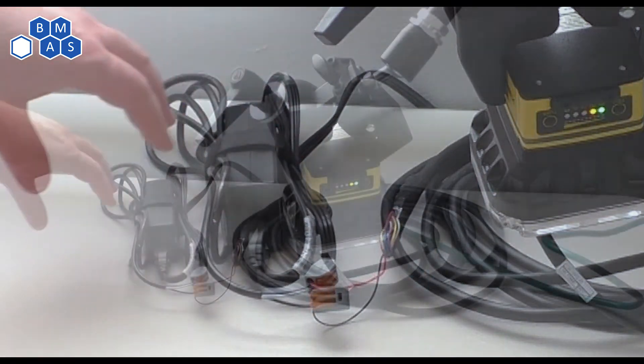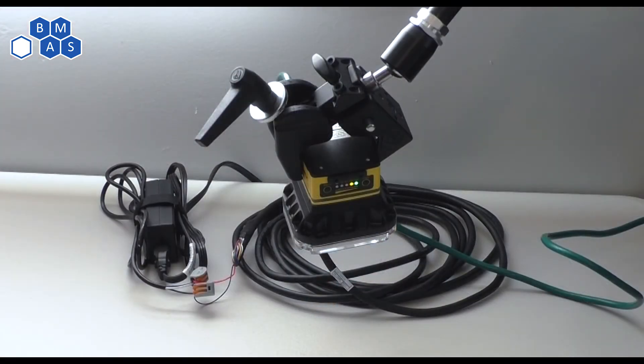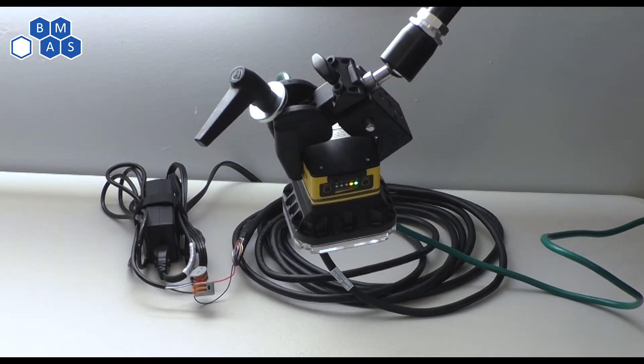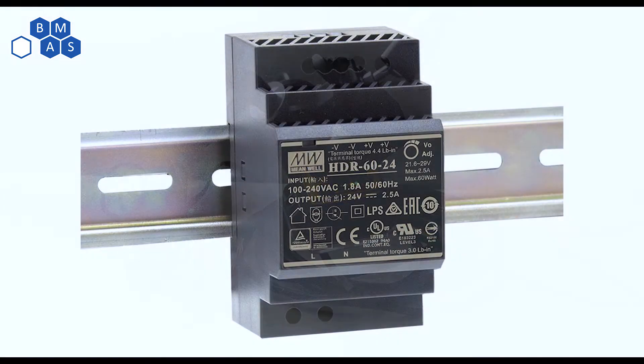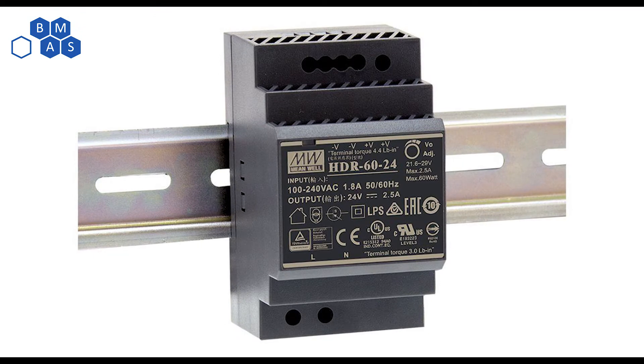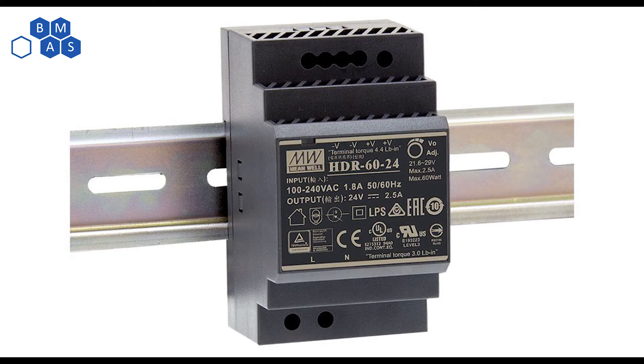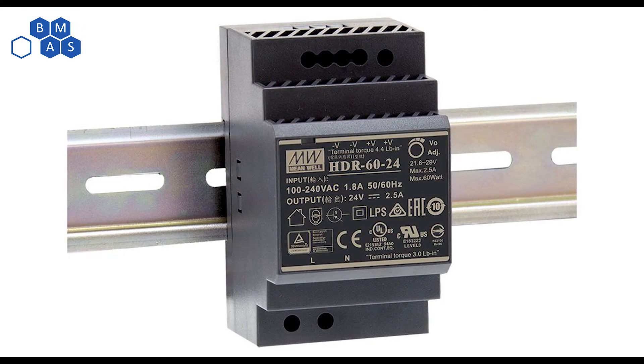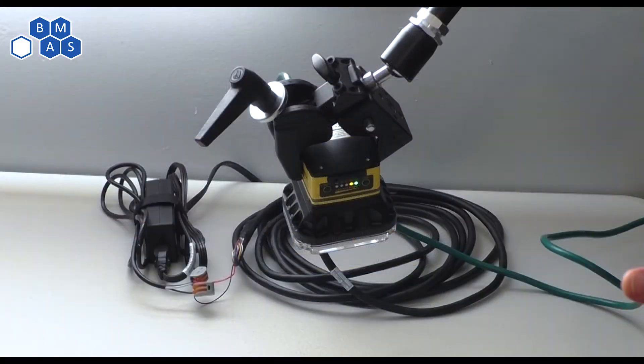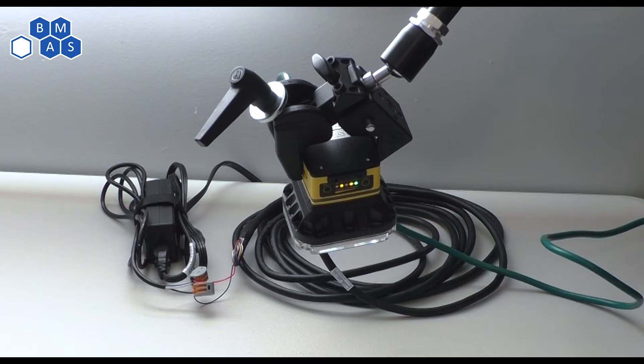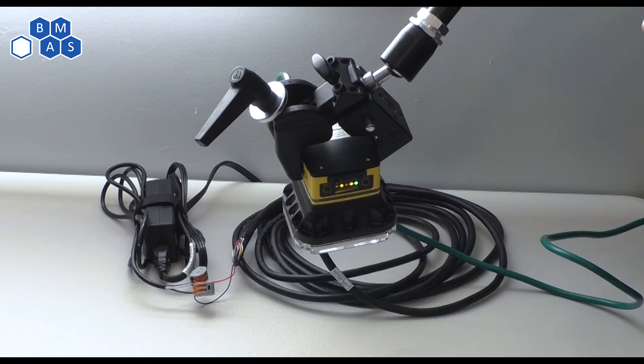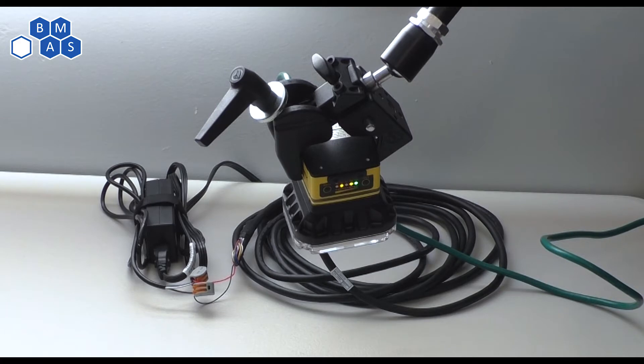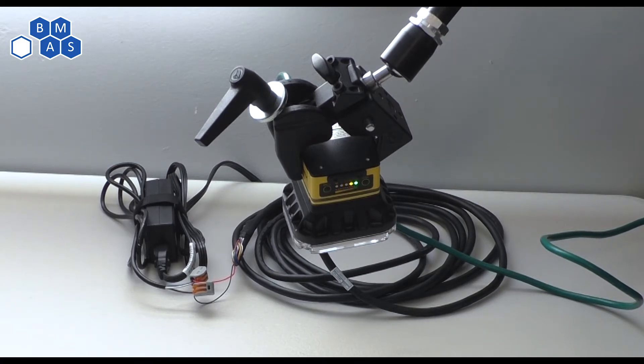And something that I think is really good to know, if you're ever going to do a benchtop thing like this just to test something or do a little development, in a real machine, we would buy a proper 24-volt power supply. It'd be DIN rail-mounted and industrially rugged. For the bench here, it's not nearly as important. It doesn't have to be that rugged. So cost is often more of a consideration. So this is a great example. I'm just using an old laptop power supply. It's 18.5 volts and 3.5 amps, which ends up being just fine for this camera. So obviously check that when you're setting something like this up, but that's a nice inexpensive solution.